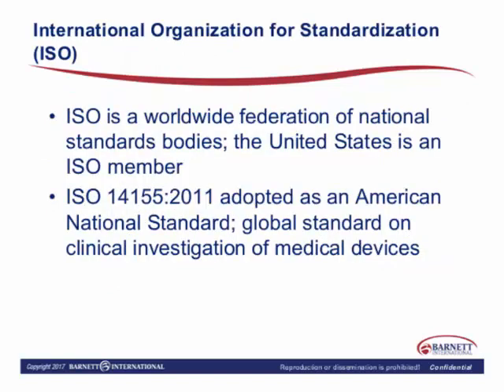ISO is a worldwide federation of national standards bodies, and the U.S. is part of ISO. ISO 14155 was adopted in 2011. Prior to this, for several years, we had ISO 14155 Parts 1 and 2, but these were merged together to give us a global standard on clinical investigation for medical device studies.